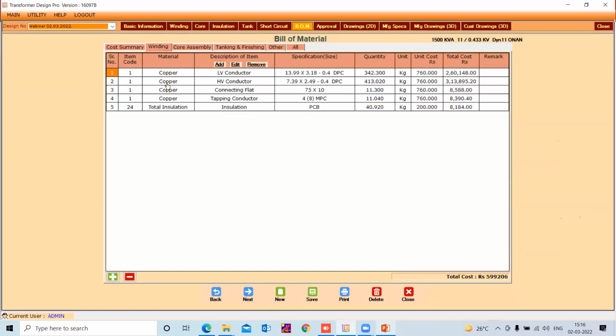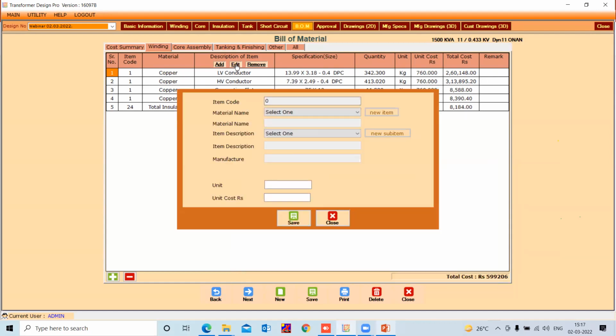Next is the winding. In the winding section, the winding related information you will get over here, like serial number, item code, material, description of item, specification, quantity, unit cost, total cost, and remark. Here also, the unit cost is editable. There are two ways to edit this price. One for this particular design and another in the database for your upcoming designs. That also I will show you, how to change the prices in the database using this add, edit, remove button. You have to click on the edit button to edit or modify this information. Let's consider HV conductor. So 760 is here. If I change it to 800, then for your next upcoming design, it will take 800 rupees.